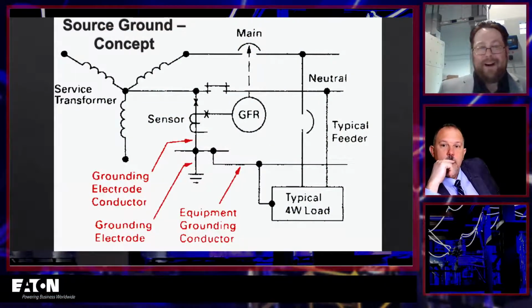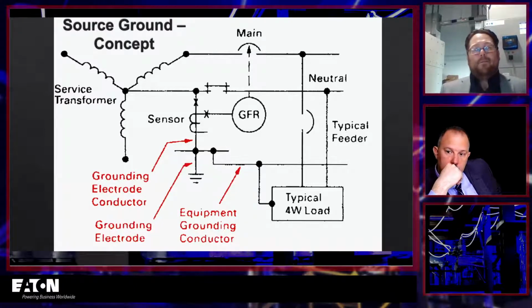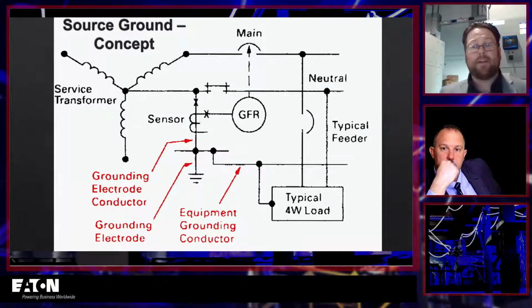That's why, when we look at the National Electric Code requirement for ground fault testing, it's when it's first installed. We're making sure that the system from the CTs through all that wiring into the breaker works, which we haven't even talked about. What happens when you have main-tie-mains and you're doing residual ground fault protection? You have multiple CTs, and if you did secondary injection, you're missing all of that circuitry. Now the code is saying you need to test that in your system and make sure it works. Beyond that, you can just do the secondary injection. That's perfectly acceptable. But that first install, that first test, we need to make sure all that other stuff, not just the trip unit, is working properly.